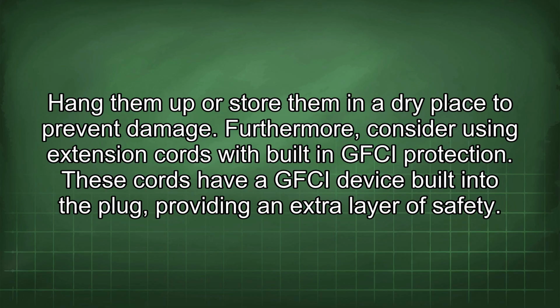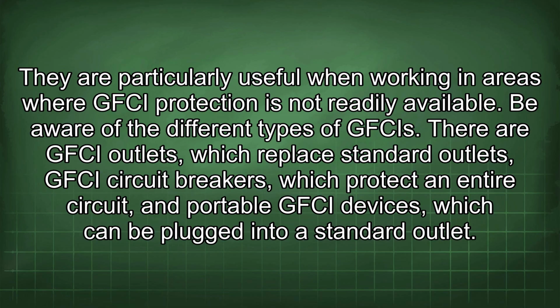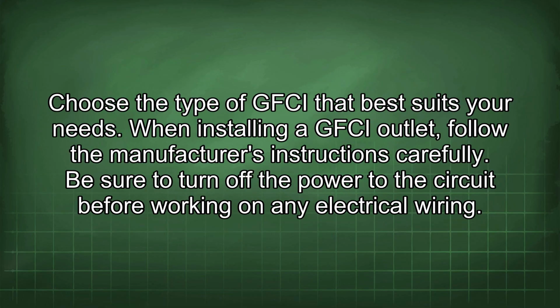Furthermore, consider using extension cords with built-in GFCI protection. These cords have a GFCI device built into the plug, providing an extra layer of safety. They are particularly useful when working in areas where GFCI protection is not readily available. Be aware of the different types of GFCIs. There are GFCI outlets, which replace standard outlets, GFCI circuit breakers, which protect an entire circuit, and portable GFCI devices, which can be plugged into a standard outlet. Choose the type of GFCI that best suits your needs.